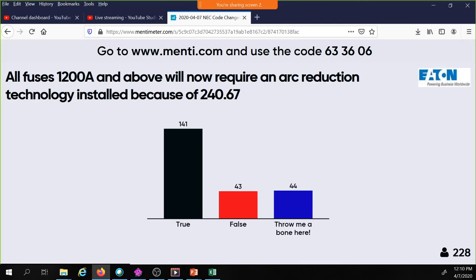And I'm telling you right now, you're jumping on the wrong bandwagon, because you should be jumping on the 43 false bandwagon, because that is not a true statement. And we're going to review 240.67, and I'm going to help you understand why not all fuses 1200 amps and above will require an arc reduction technology installed because of 240.67.